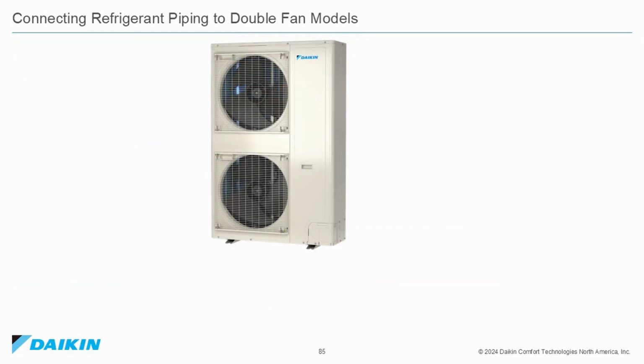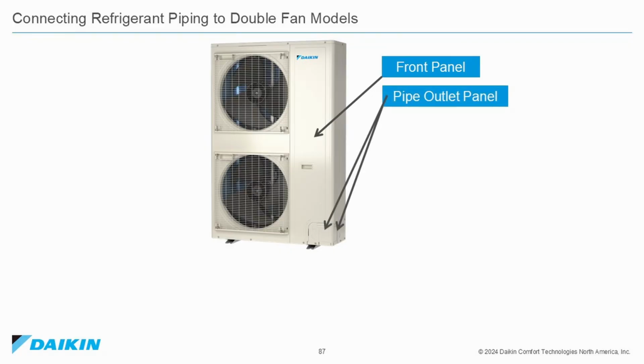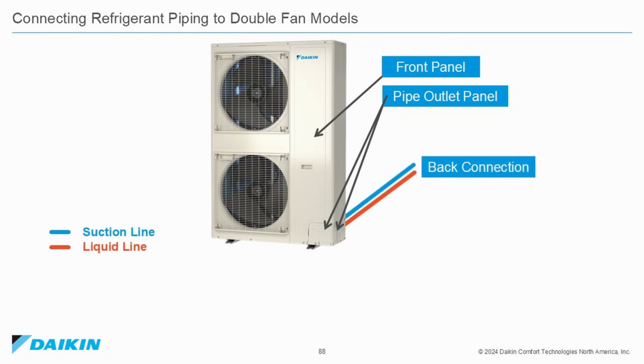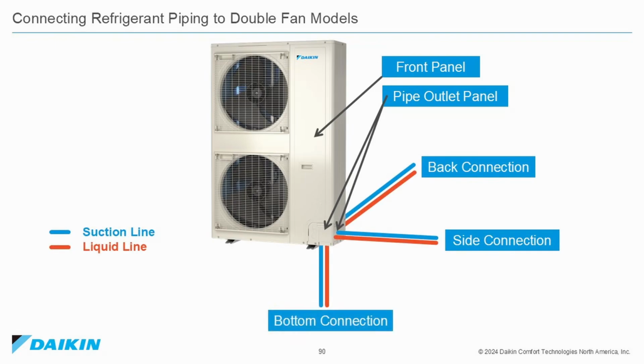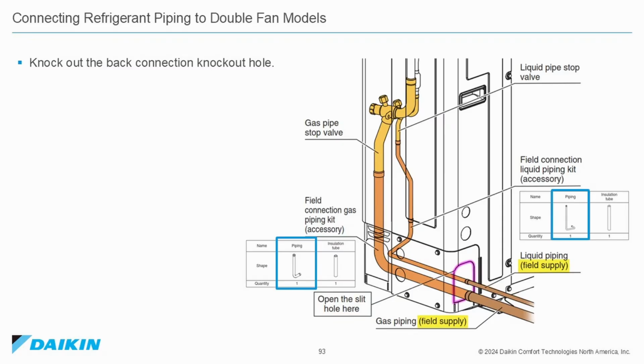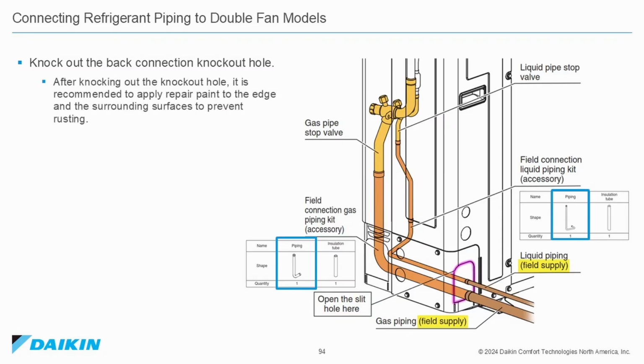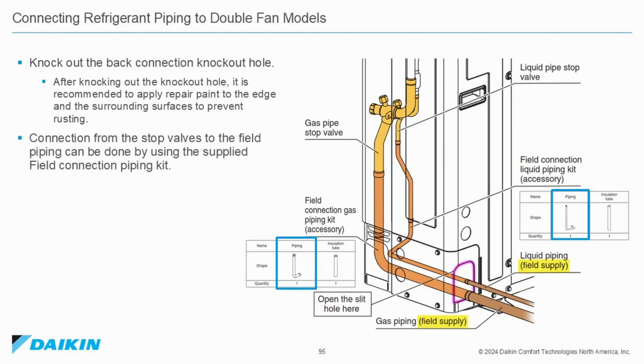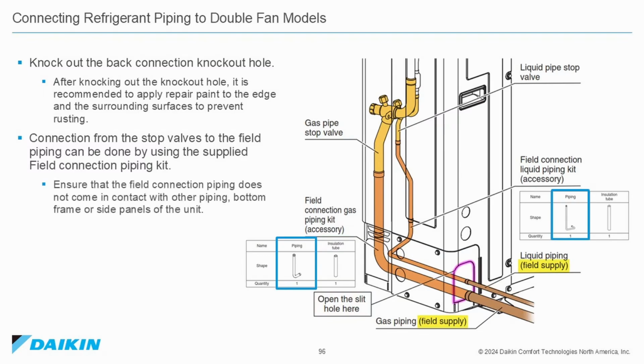Connecting refrigerant piping to the double fan models. Here you'll see the front panel, the pipe outlet panel that covers the front, side, and the back. You do have back connections, side connection, bottom connection, and front connection. Knock out the back connection knockout hole. After knocking out the knockout hole, it is recommended you apply repair paint to the edge and surrounding surfaces to prevent rusting. Connection from the stop valves to the field piping can be done by using the supplied field connection piping kit. Ensure that the field connection piping does not come in contact with other piping, bottom frame, or side panels of the unit.